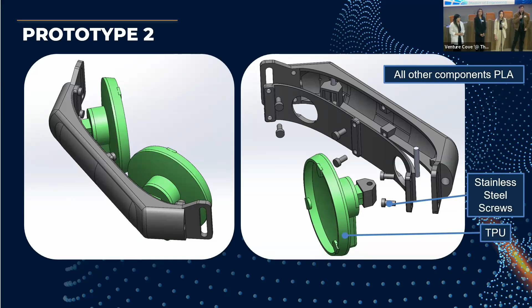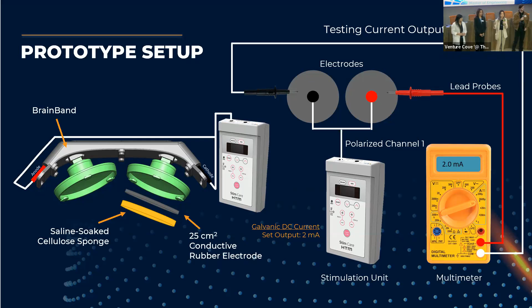To see how all this works, what we could do is turn on the stimulation unit to a 2 milliamp direct current output. This should send it to the electrode, in which we can use a multimeter to complete the circuit. Here we can get an output reading, and if that reading matches for the electrodes to the stim unit, it indicates that the whole system does work. And from our testing, our prototype does work.